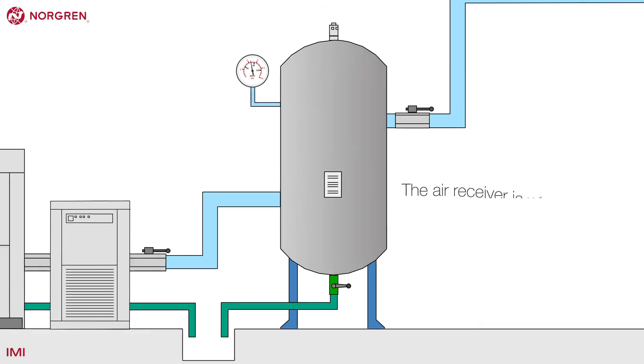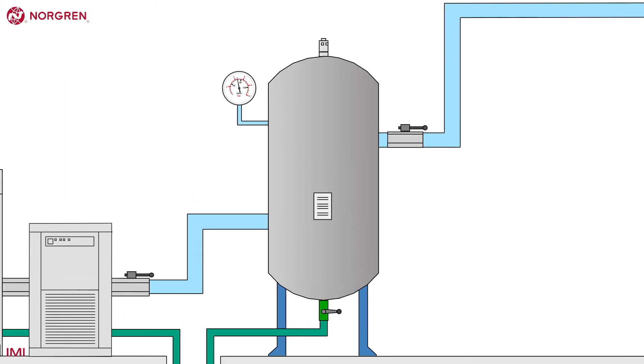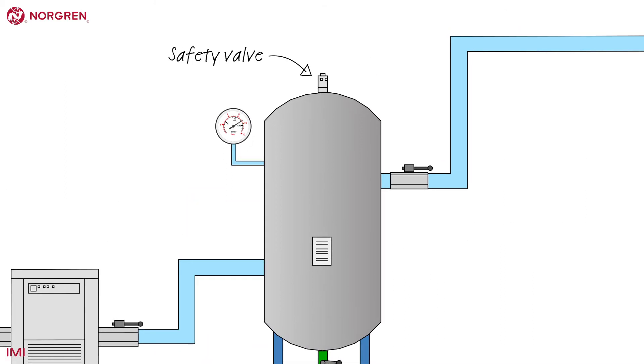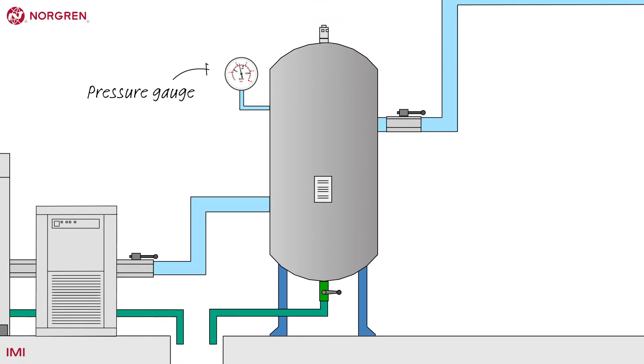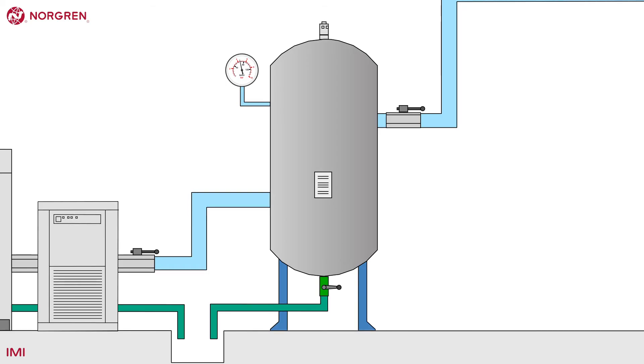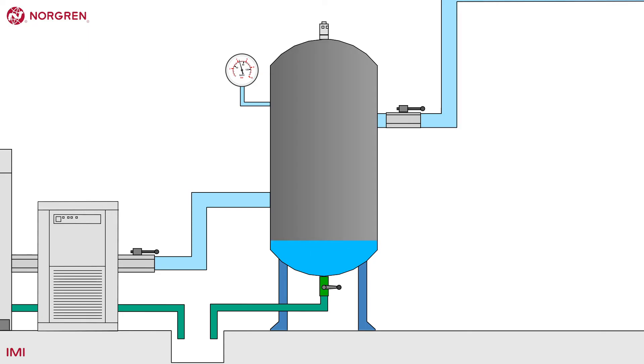The air receiver is where the compressed air is stored — think of it as a battery; it's where the energy is stored. The safety valve will release air if the pressure rises above the set pressure, for example 10 bar. The pressure gauge displays the pressure inside the tank. It's advisable to locate the air receiver in the coolest place possible without dropping below freezing. Cool air holds less water and is denser. In the receiver the water condenses and drops to the bottom of the tank, and so less air is stored in this space.